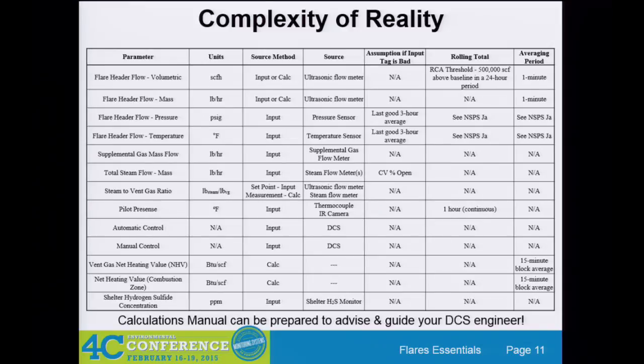So now what do you do? You need the rest of your system to keep working, and just because you lost your pressure measurement, you don't want to have to put everything on manual. You want to let it function. So is there a value you can use that can keep the system functioning well? Maybe not the best, but at least good enough to keep things moving? Or is it basically a critical failure where you cannot operate without that parameter?